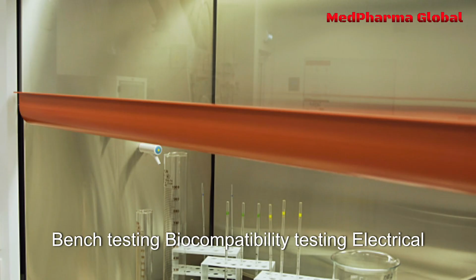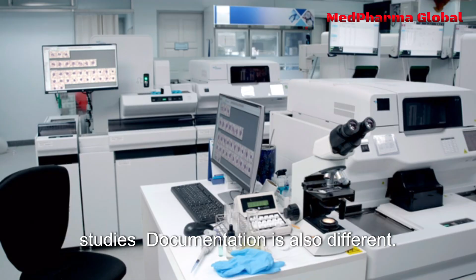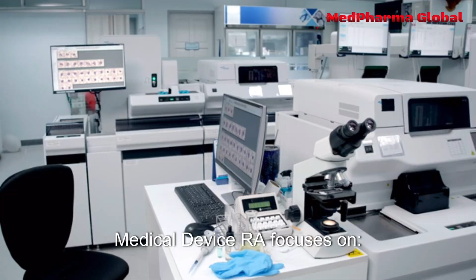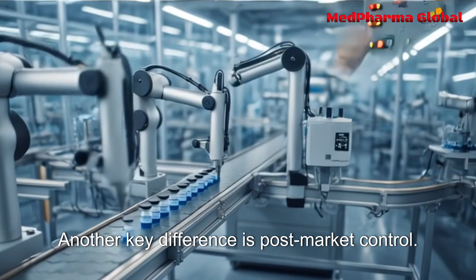Unlike drugs, many devices are approved through bench testing, biocompatibility testing, electrical safety testing, software validation, and human factor studies. Documentation is also different. Medical device RA focuses on the design history file (DHF), device master record (DMR), risk management file (ISO 14971), clinical evaluation report (CER), and post-market surveillance. Standards compliance such as ISO 13485 is a major part of device regulation. Another key difference is post-market control. Devices require vigilance reporting, field safety corrective actions, and unique device identification (UDI).